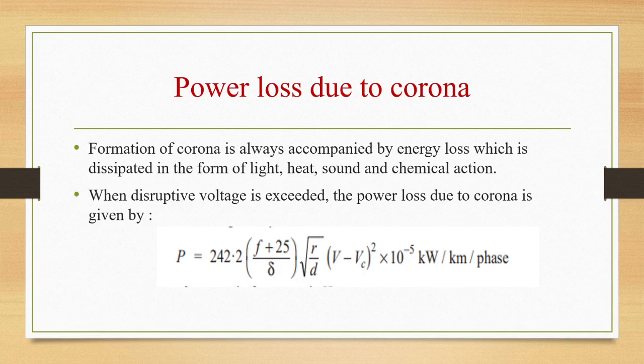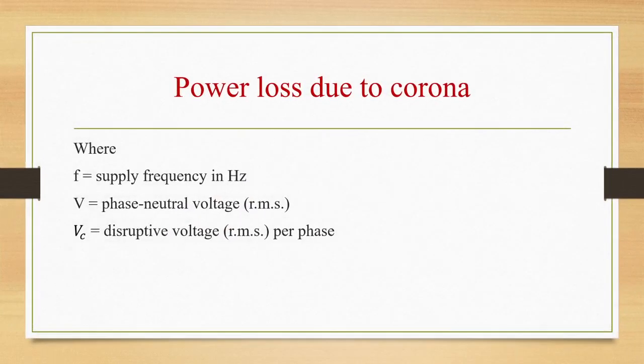So when the disruptive voltage is exceeded, power loss due to corona will be given as P is equal to 242.2 by delta into (f plus 25) into root of r by d into (V minus Vc) square into 10 power minus 5 kilowatt per kilometer per phase, where f is the supply frequency in hertz, V is the phase neutral voltage RMS value and Vc is the disruptive voltage RMS value per phase.